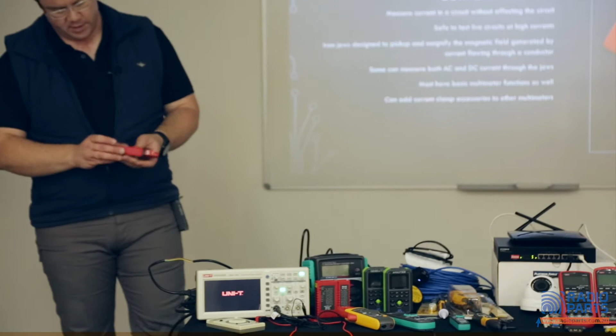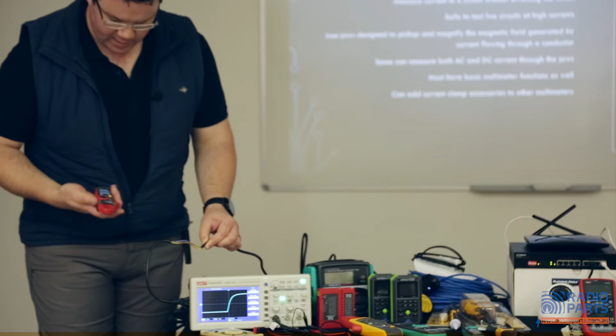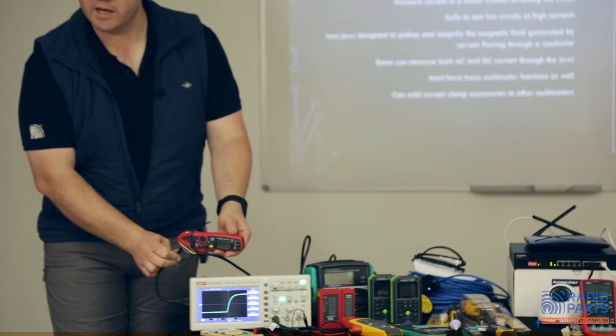Now I take the same meter I was using before. I've got 3 wires in here: active, neutral and ground. If I clamp this over my brown lead - it's supposed to be in the center, but it gives you an idea - now I can see there's actually current flowing through that lead right now.